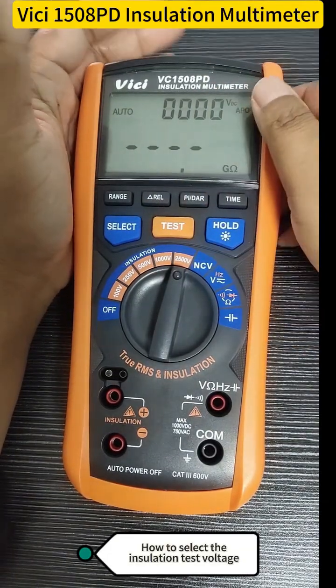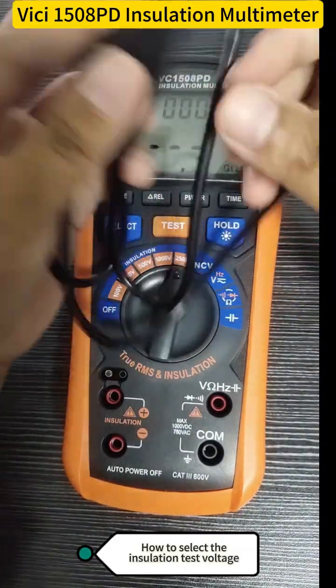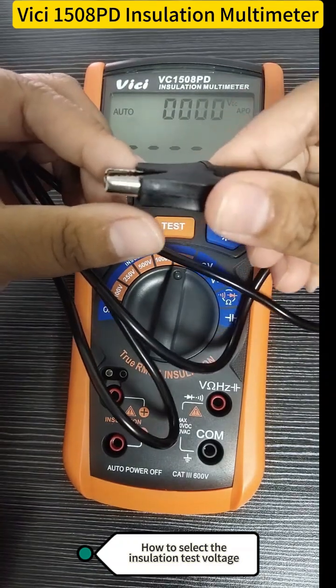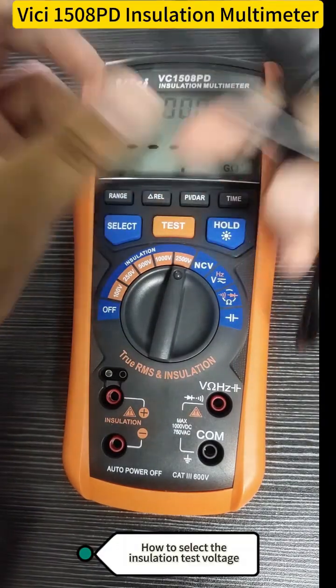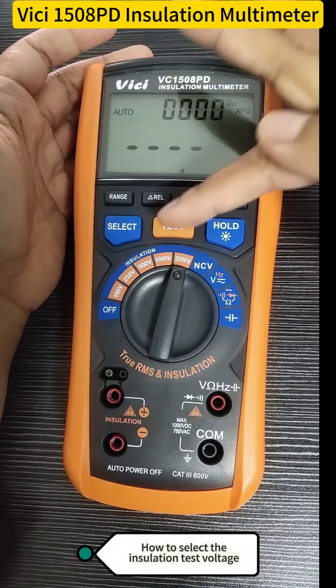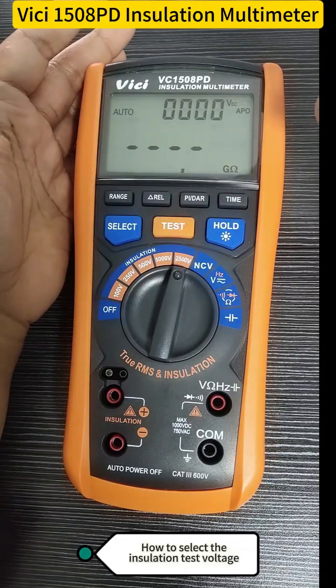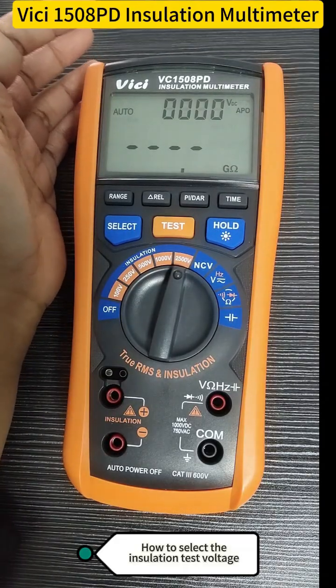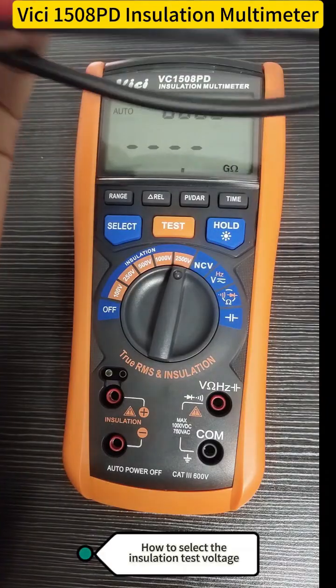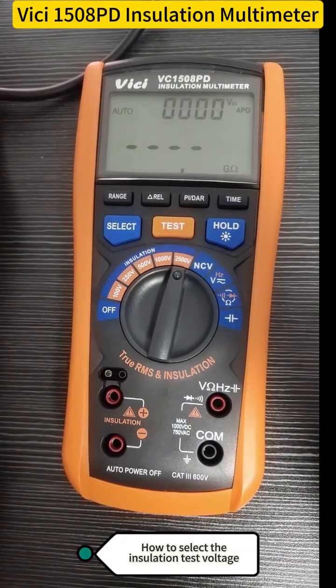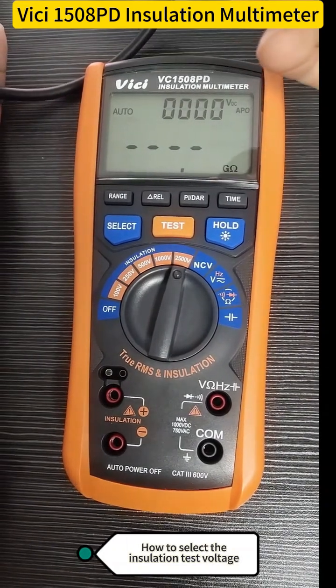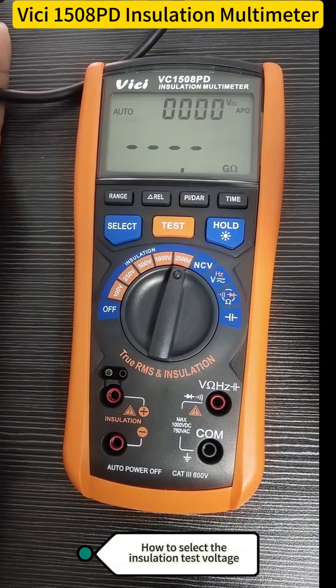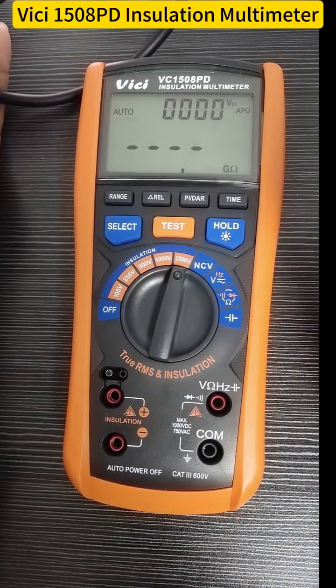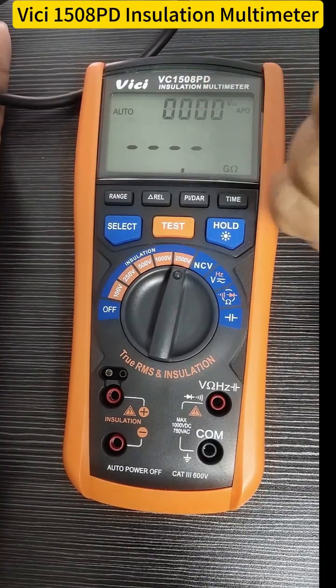Then here's a small tip. Clip this alligator to the equipment. This alligator needs to connect to the equipment casing or the ground wire. Then touch the probe to the target wire. We do not have to reach for the meter's test buttons here for the high voltage work or the remote operation. Just press this test button on the remote probe to start the insulation measurement. The number on this screen is the insulation resistance in megohms. For most motors, if the reading drops below 0.5 megohm, the insulation is bad and leaking current. You need to fix that right away.